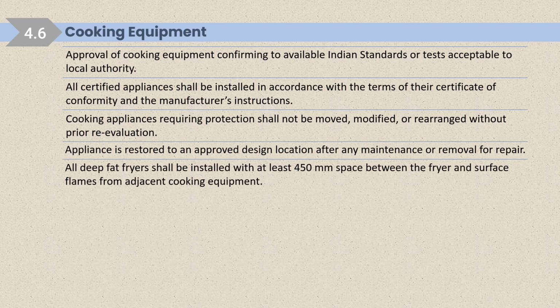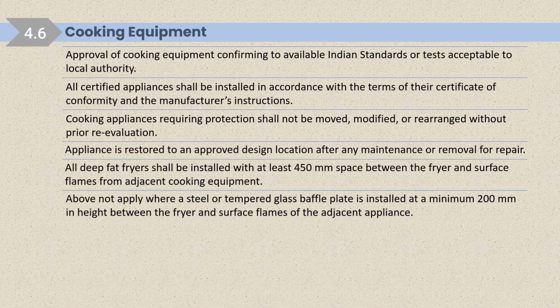All deep fat fryers shall be installed with at least 450 mm space between the fryer and surface flame from adjacent cooking equipment. We should note this point. This is saying if a deep fat fryer is in use, then any other equipment which releases flame should be spaced at least 450 mm. So deep fat fryer or any flame releasing equipment should be spaced at least 450 mm.